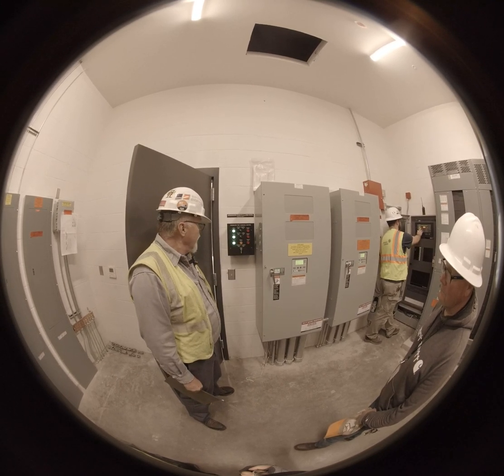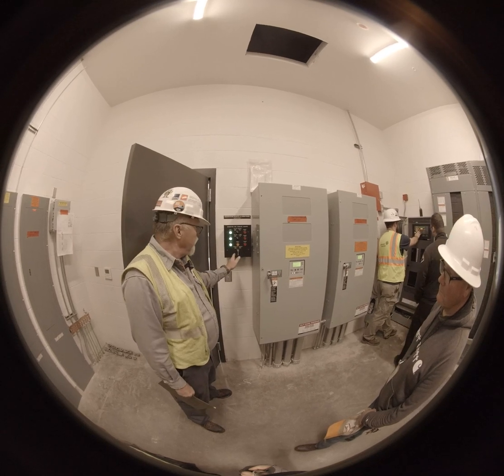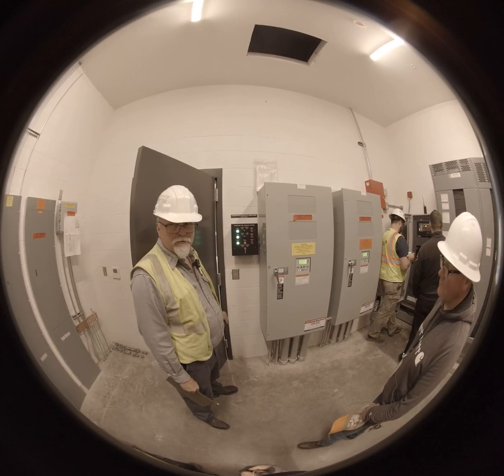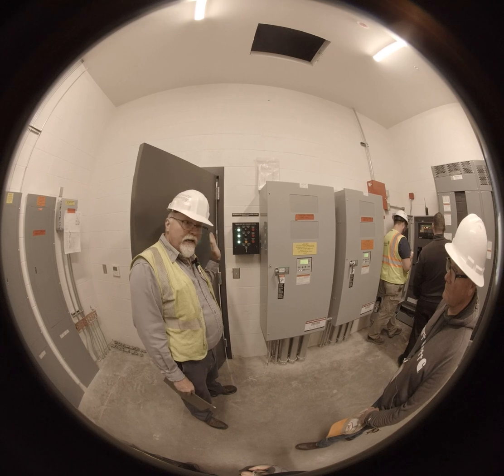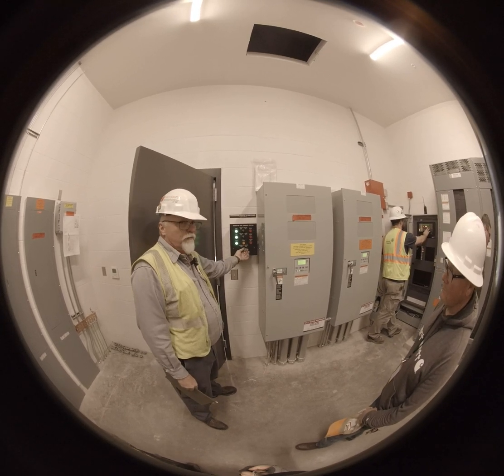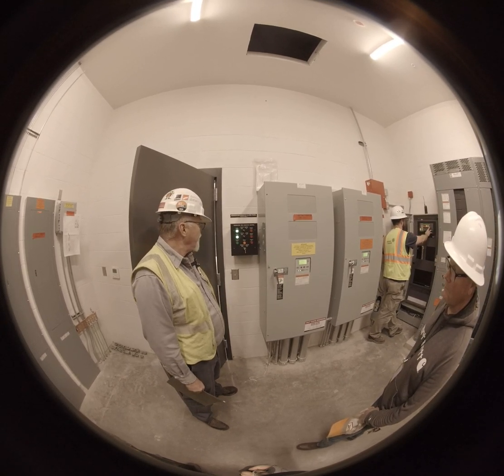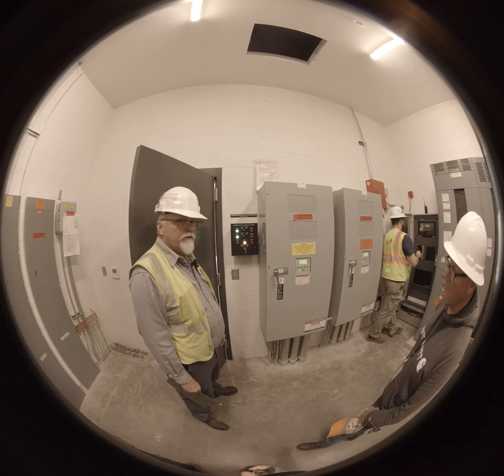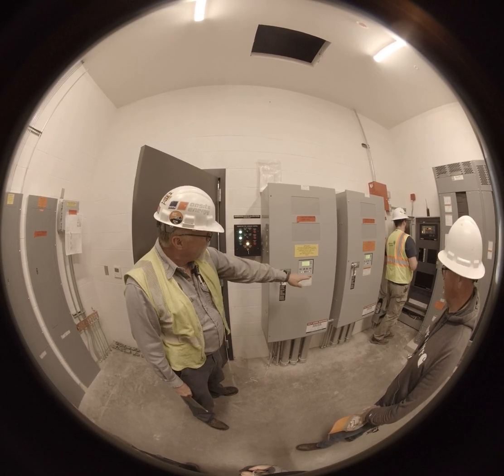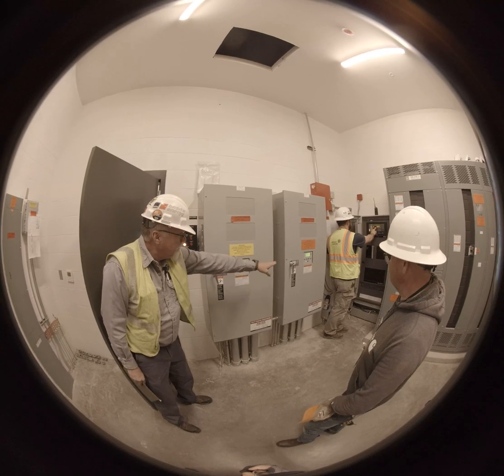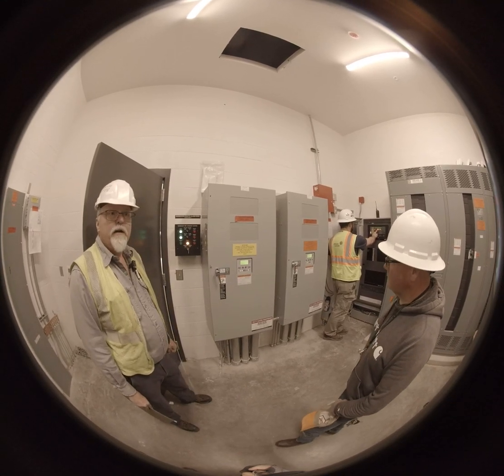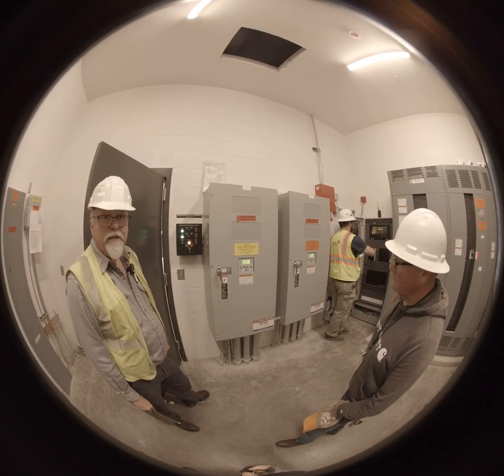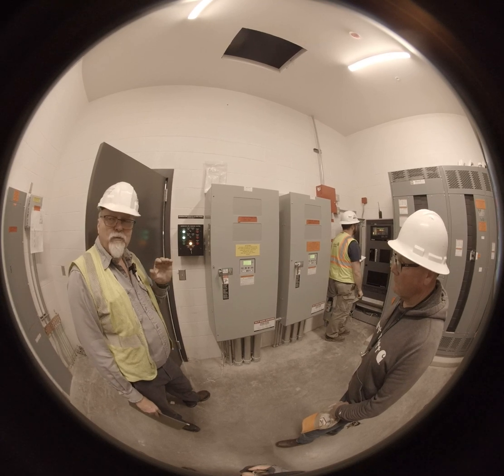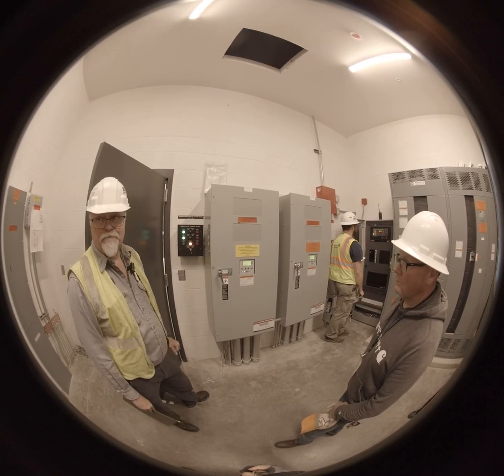Okay, so I'm going to go ahead and fire the generator up. It should just turn the light on. Everything should be like it's supposed to. We have the generator closed up outside. We have the boxes closed up. So we will... Generator's running. If you look over here, you'll see we have a red light. It shows that generator power is available and is within parameters to transfer.